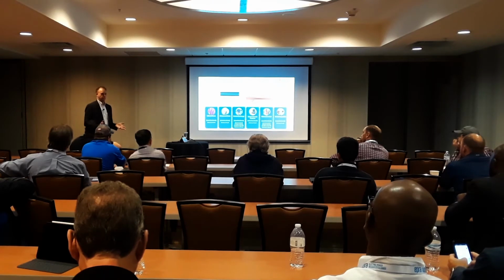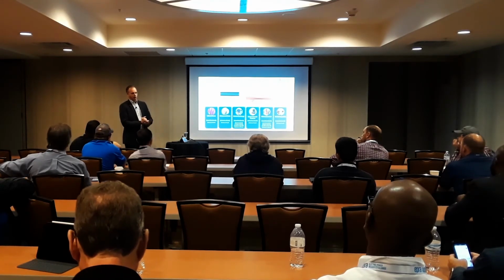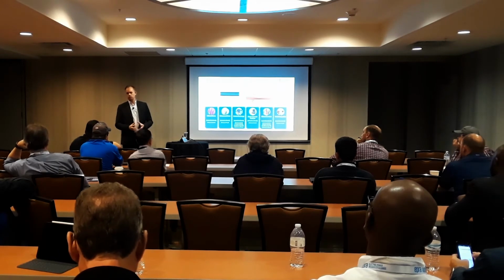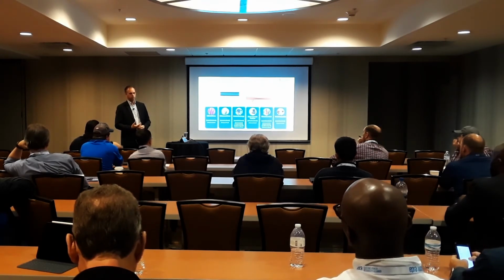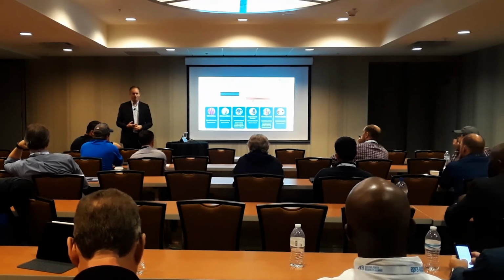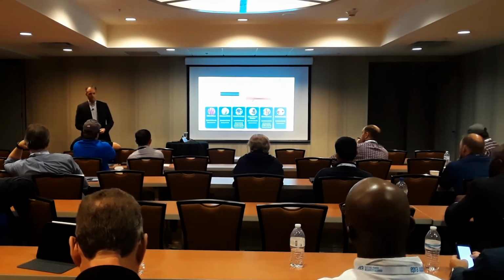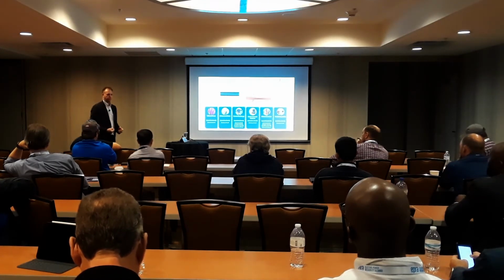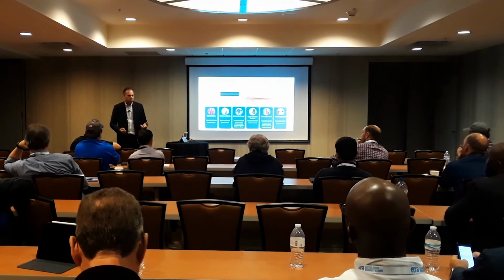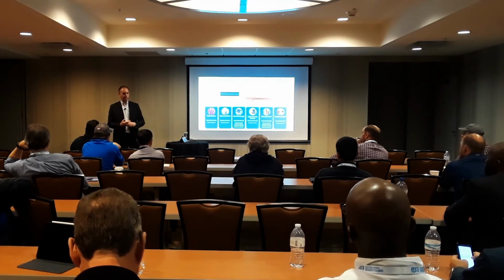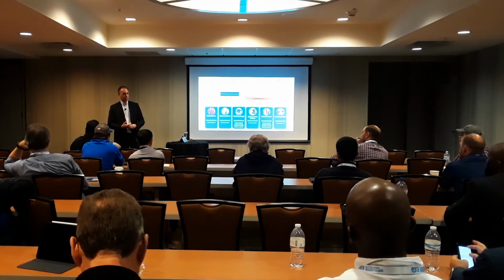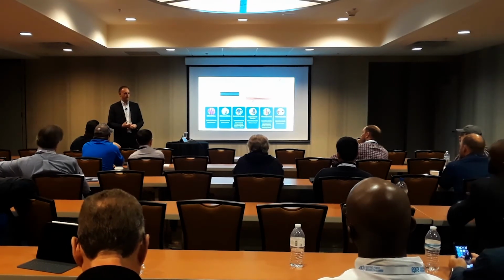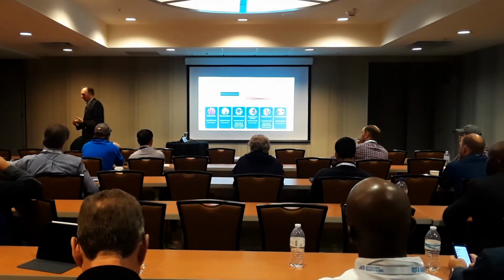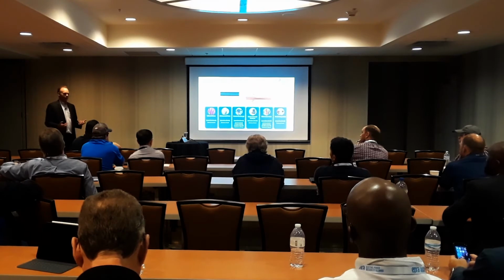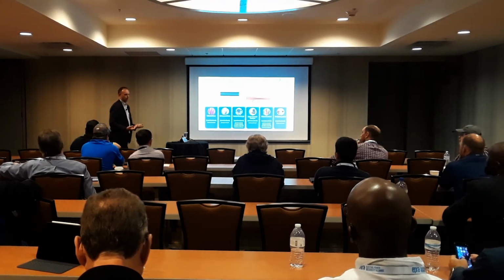So what can I do as the maintenance manager responsible for that asset to make it any better? Is there anything I can do? No. Just because it's November and we've got our Thanksgiving shutdown coming up in a week and a half, should I do anything to that piece of equipment just because I have that scheduled outage? No, why would I go in there and tighten or clean or generally disturb that equipment in any way if there's no indication of any kind of defect?